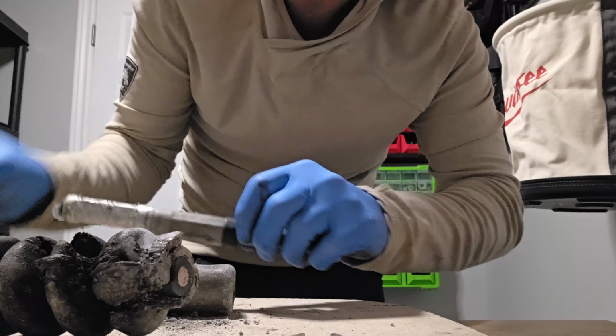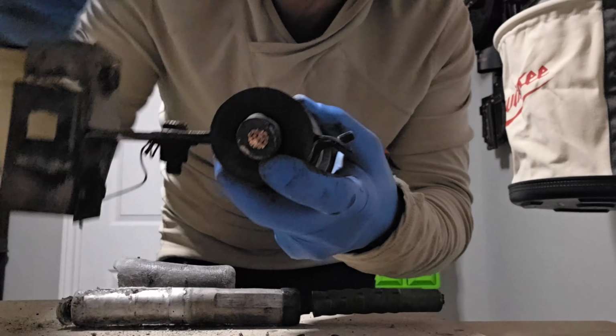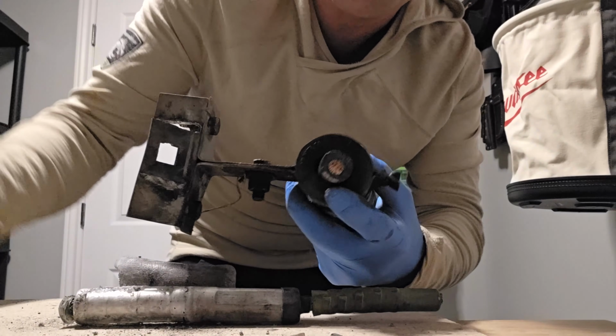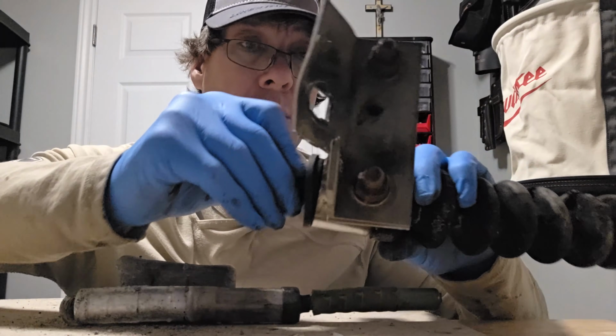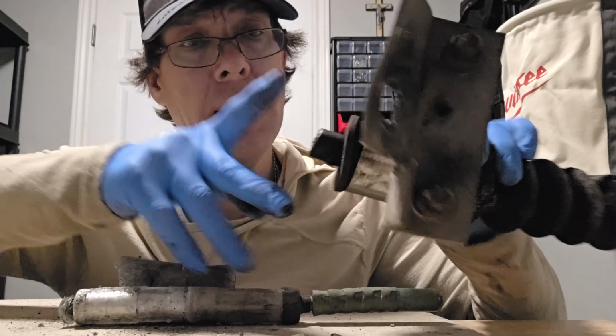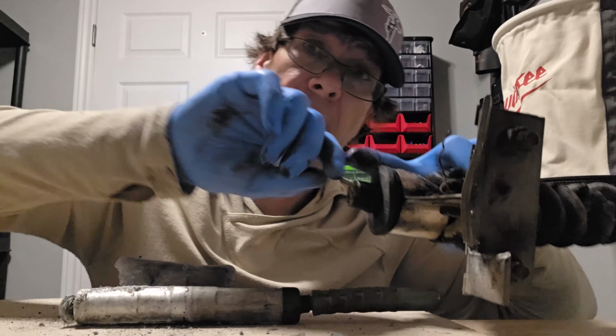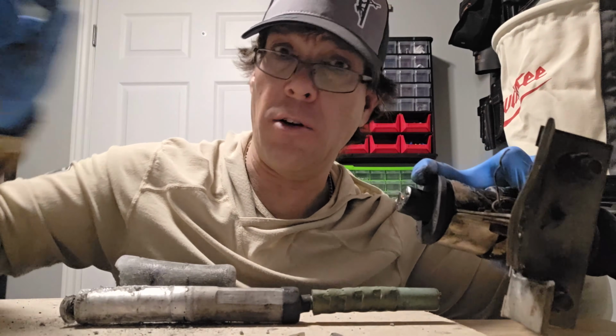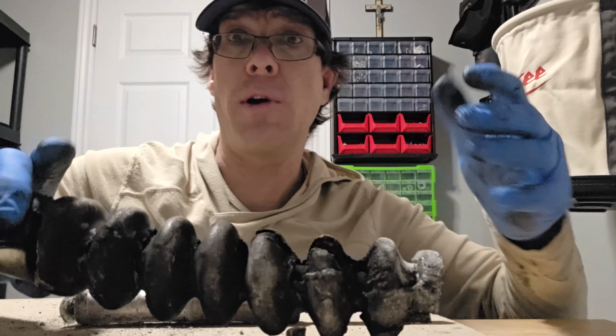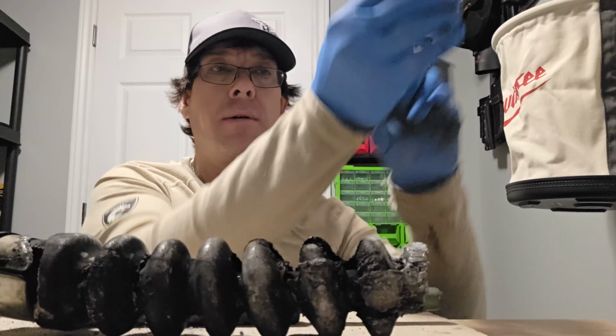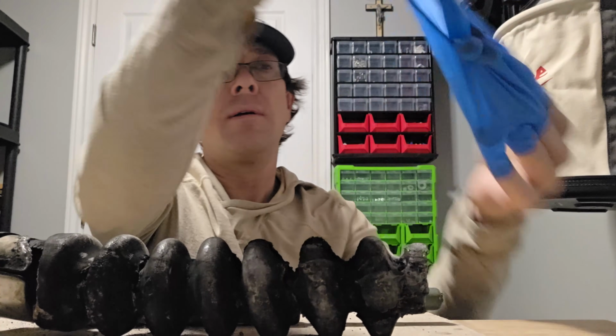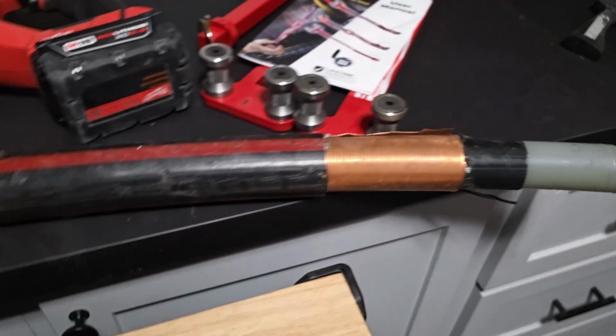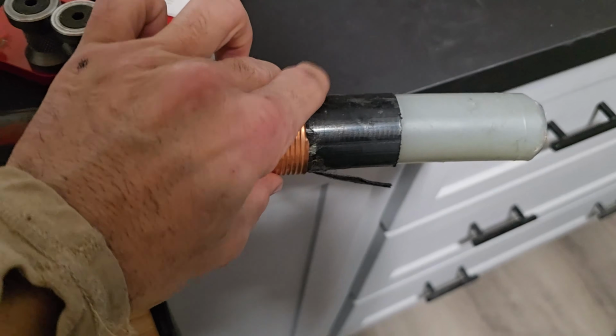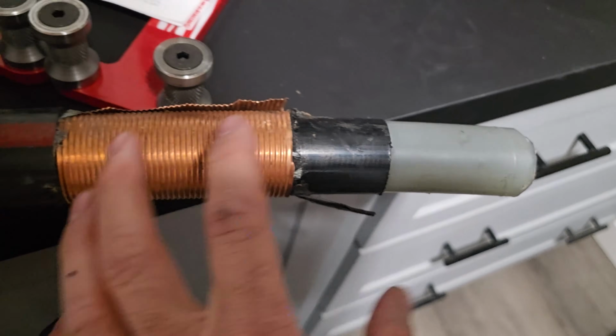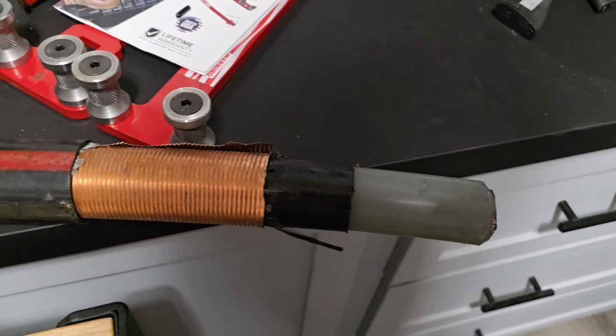So all we did in order to fix that, you can see we cut it off flush there. The difference between this cable and the one I just showed you guys is the neutral was already stripped back, and we use that actually as a neutral going to the school. But we simply cut that off, and then we peeled the jacket back another 11 inches, had the neutral coming out, and then redid the termination process, which looks like that pretty much. So we had that peeled back. There was a lot more insulation exposed than that. We crimped on the lug, put up brand new terminations.